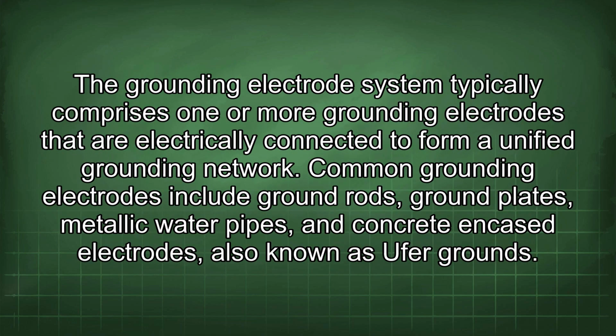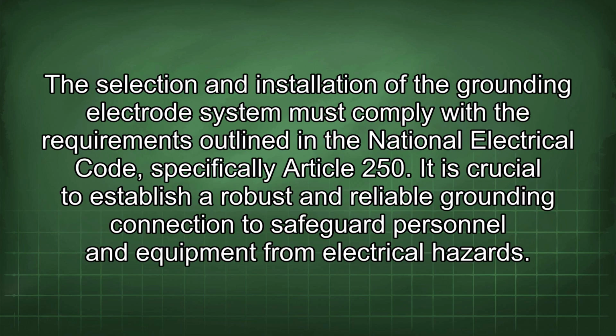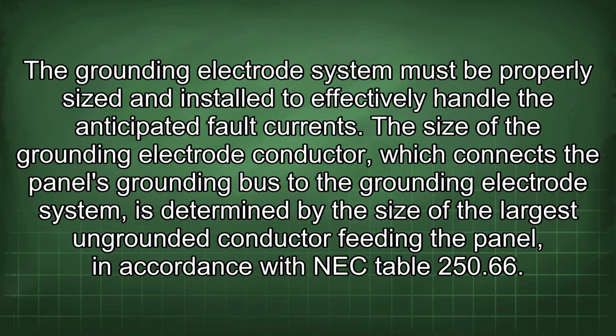The grounding electrode system typically comprises one or more grounding electrodes that are electrically connected to form a unified grounding network. Common grounding electrodes include ground rods, ground plates, metallic water pipes, and concrete encased electrodes, also known as Ufer grounds. The selection and installation of the grounding electrode system must comply with the requirements outlined in the National Electrical Code, specifically Article 250. It is crucial to establish a robust and reliable grounding connection to safeguard personnel and equipment from electrical hazards. The grounding electrode system must be properly sized and installed to effectively handle the anticipated fault currents.